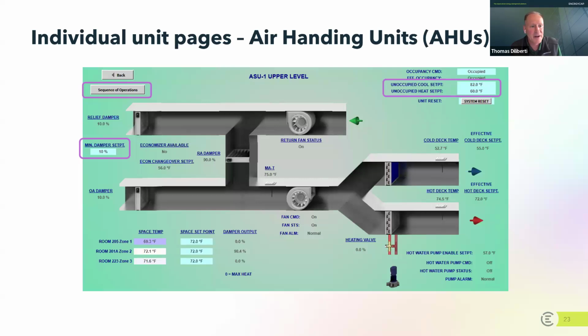Okay, this slide talking about air handling units. I just wanted to bring to your attention these unoccupied set points. Again, just as an example, they're in the system, they're programmed in at 60 and 82. Also wanted to bring to your attention this idea of, you've probably noticed in many of these screens, there was a button for a sequence of operations. This is just the first time I happened to flag it. But this button in this system allows the user to go in and actually see how this particular unit is programmed. Love that idea. Love keeping the documents and all the logic available for people to look at.